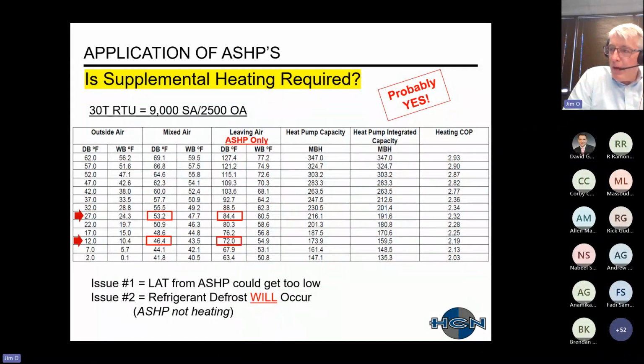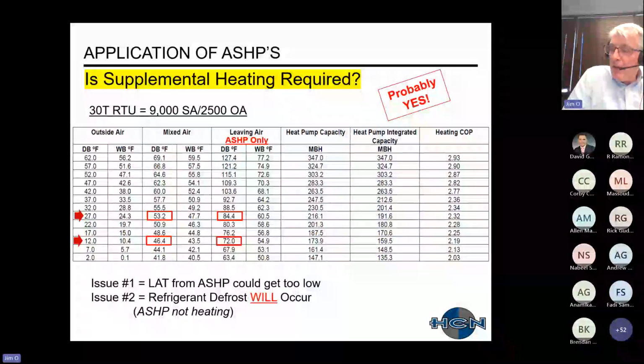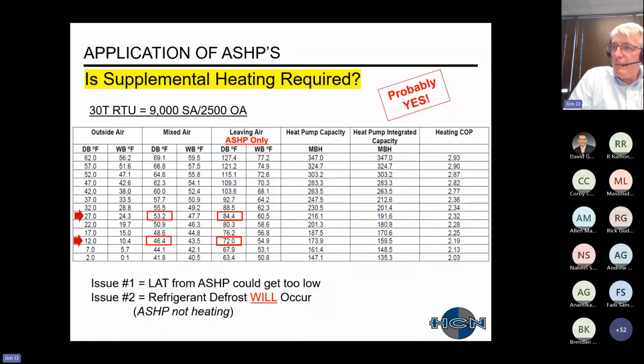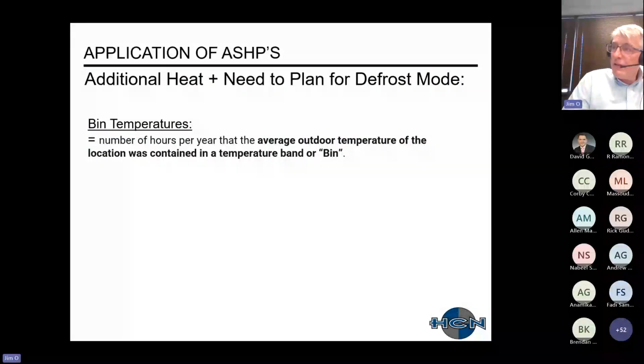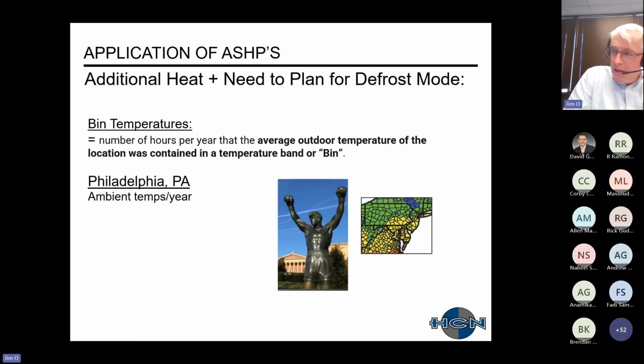So once again, the air source heat pump is not heating. At these two temperatures, you would expect that during some time of its operation, the unit's going to go into defrost mode to try to warm up the refrigerant. So, planning for defrost mode, once again back in Philly, I live near the Rocky statue in downtown Philly, but looking at just bin temperatures. Bin temperatures, if you're not familiar with the definition, are the number of hours per year that the average outdoor temperature of the location was contained in a temperature band or bin.